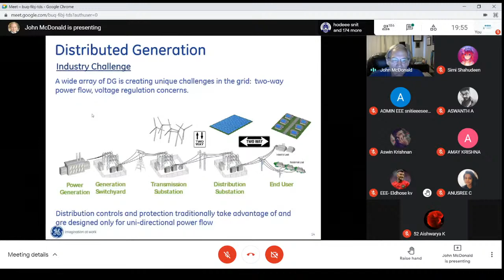Open circuit over voltage due to unintentional islanding. What's really critical is protection ratings may not match fault currents. Why? When you're doing a protection study to determine the settings for the relays, you have to do a short circuit study first. You have to know what the anticipated fault currents will be at different parts of the grid.